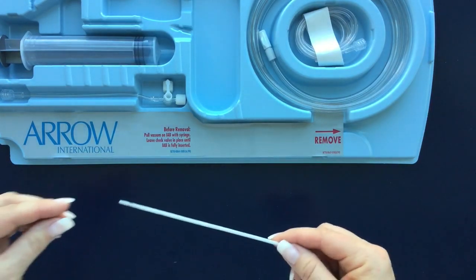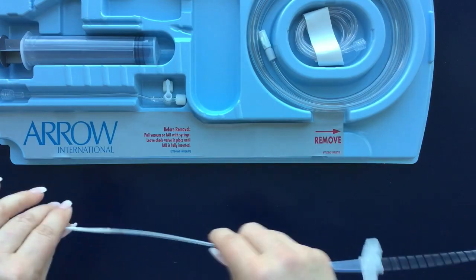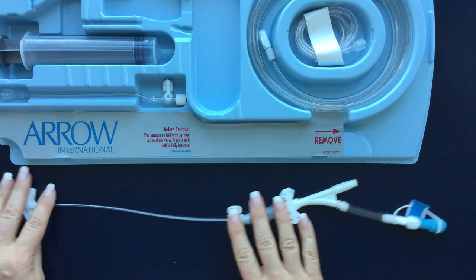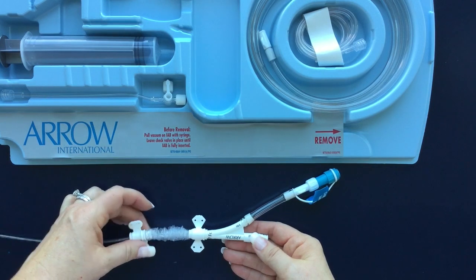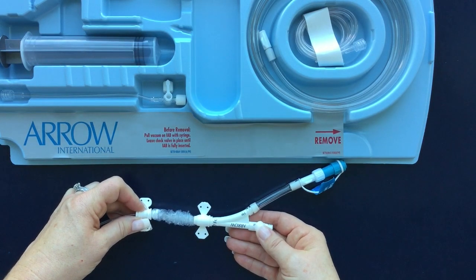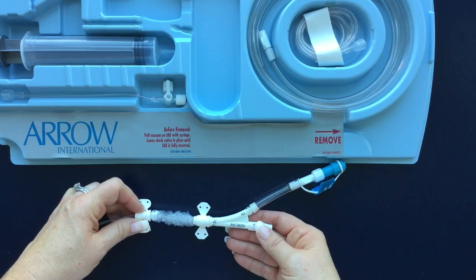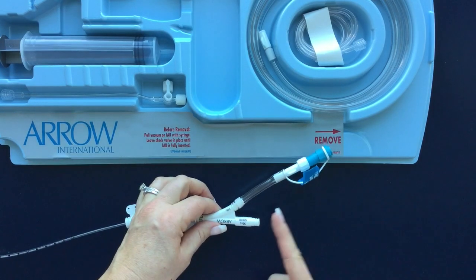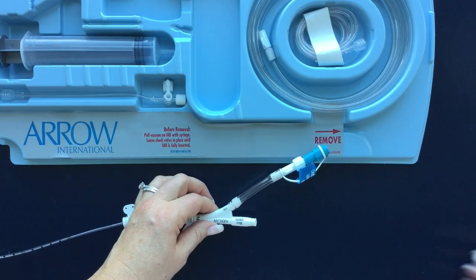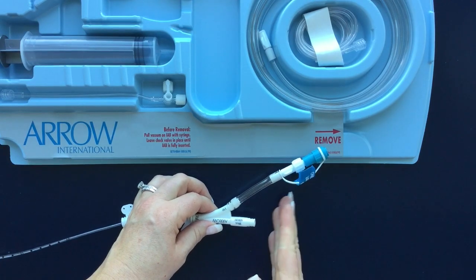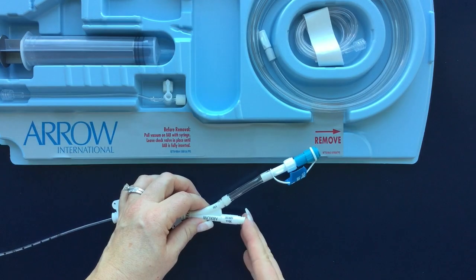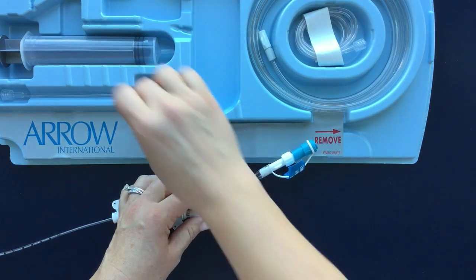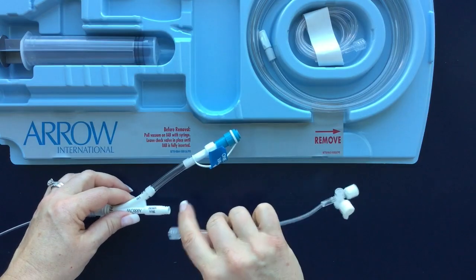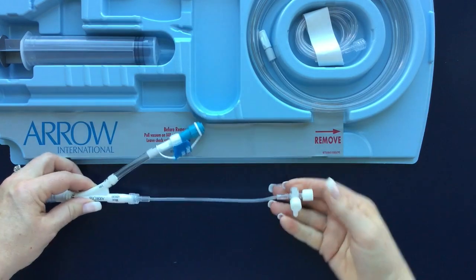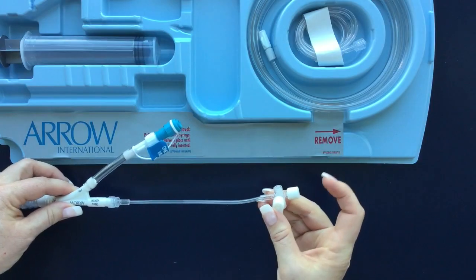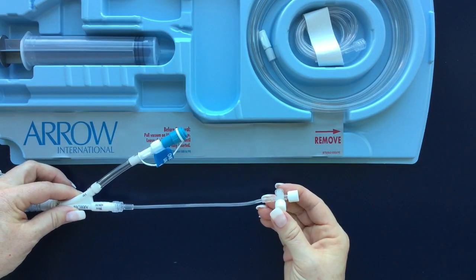This is when we are now ready to load the balloon onto the guide wire and hand off to our physician for insertion. Once the catheter is in place, the tip of the balloon located at the 2nd to 3rd intercostal space, or 1 to 2 centimeters below the left subclavian offshoot, I can now remove the guide wire from the central lumen and connect a pressurized transducer system, therefore enabling us to see an arterial pressure waveform on a console. This 6-inch extension in our kit can be flushed and utilized at the central lumen to aspirate and flush, and then your transducer set can connect to the stopcock here.